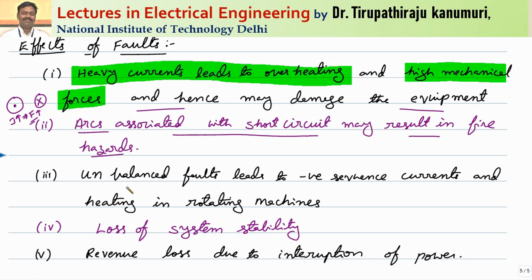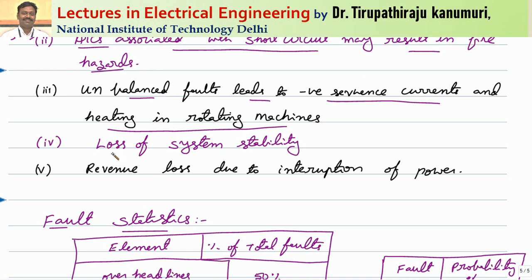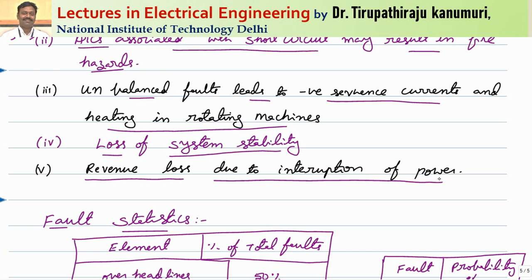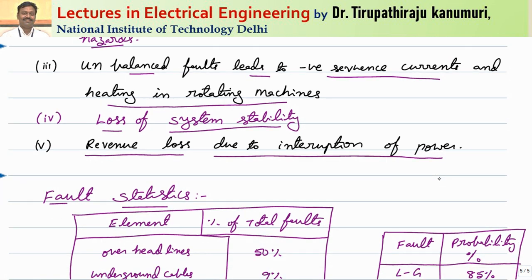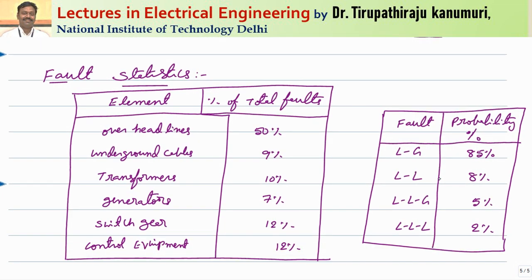Arcs associated with short circuits may result in fire hazards. Unbalanced fault currents lead to negative sequence currents and hence heat in rotating machines. In interconnected systems, if a faulted part is not disconnected, it leads to complete instability due to mismatch in frequencies of different alternators or stations — causing loss of system stability. There will also be a loss of revenue due to interruption: the generating station loses income, and industries lose production capability.